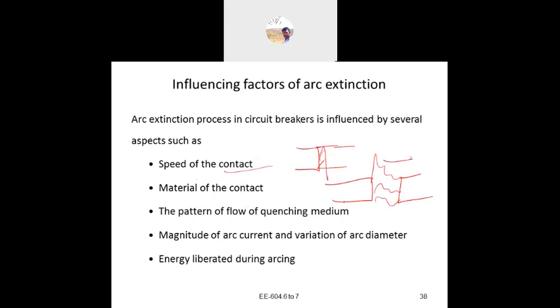Then the material of the contact: which type of material, either brass, aluminum or copper, based on the conductor. And the pattern of flow of the quenching medium: which type of quenching flow, airflow, pressurized airflow or gas, whichever quenching medium is used. If there is only natural air, the arc extinction is also very slow. Next, the magnitude of the arc current and its variation: how much arc current there is, whether the magnitude is high or low, and based on that also.